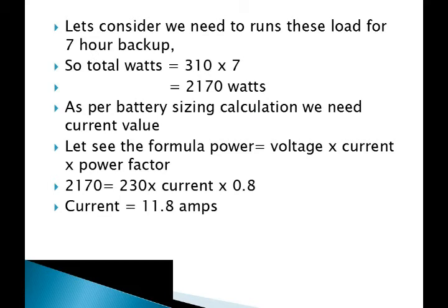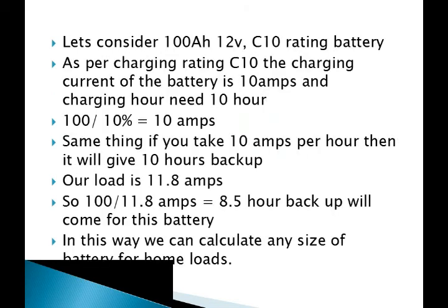As per the load, we need to size the battery. For battery sizing we should calculate the amperes. As per the formula: Power equals Voltage multiplied by Current multiplied by Power Factor. We know the power is 2170W and voltage is 230V, and power factor is 0.8. Using the formula, we get Current equal to 11.8 amperes.